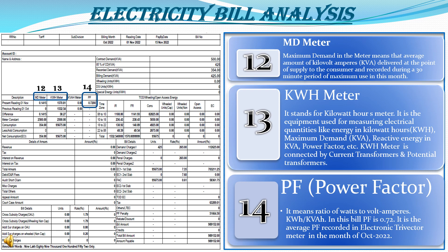The KWH meter also measures power factor and is connected by current transformers and potential transformers. Power factor is a very important term in the electricity bill. Power factor means the ratio of kilowatt to kilovolt-ampere, that is KW by KVA. In this bill, the power factor is 0.72, which is very less. We will discuss the power factor matter at the end of the video. It is the average PF recorded by the electronic trivector meter in the month of October 2022, displayed as 0.72 in the electricity bill.